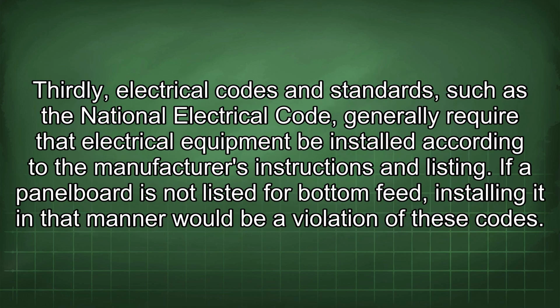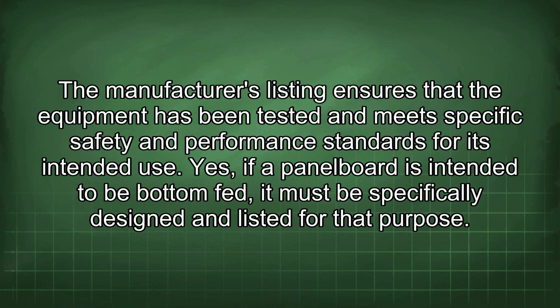Thirdly, electrical codes and standards, such as the National Electrical Code, generally require that electrical equipment be installed according to the manufacturer's instructions and listing. If a panel board is not listed for bottom feed, installing it in that manner would be a violation of these codes.